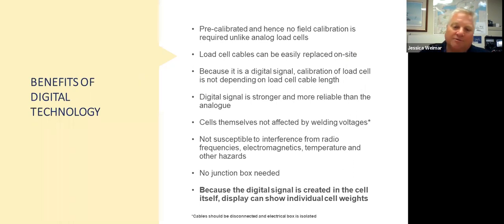And one of the things that's also important is if you consider a strain gauge system, they function with something called a summing box. What that summing box does is takes those 3 analog signals in or 4, however many cells you have, takes those wires in and converts them to digital in the junction, in the summing box it's called. We don't have that. We have a junction box because we've got to have a place to bring all 4 wires in, but all it is is a place to bring the 4 digital signals in. What's really cool is that our display can actually see all 4 cells individually, and I can see each individual weight range. Why is that important?